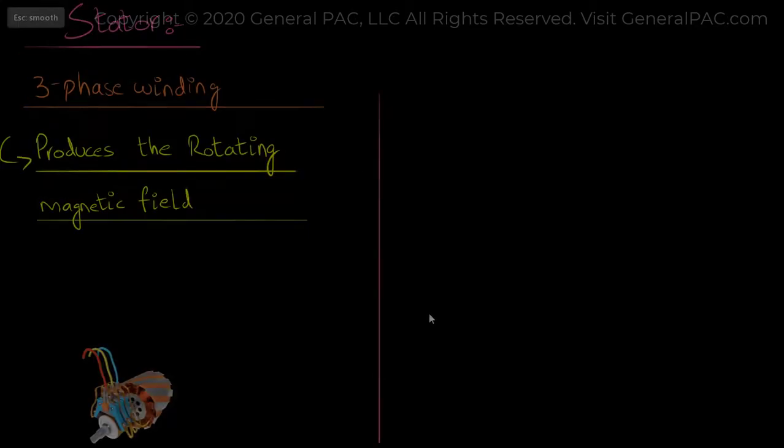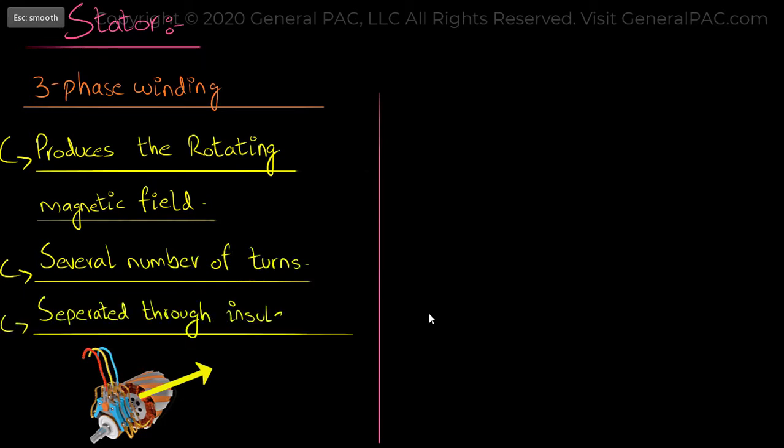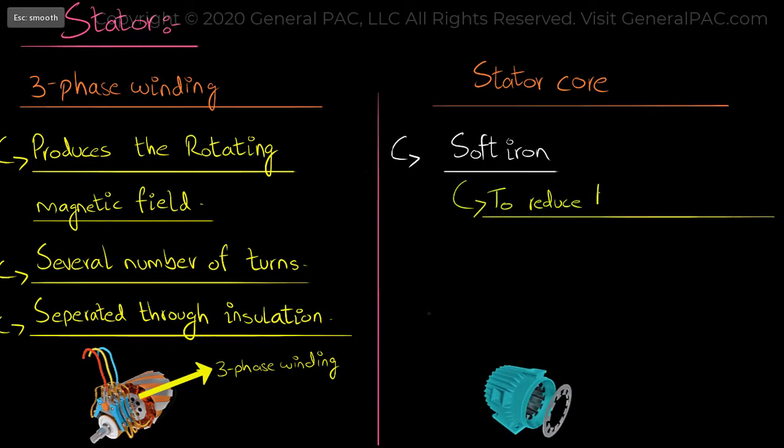Each of these phase windings have several number of turns and each turn is separated with the other through insulation. As we know that flux passes through a metal easily as compared to air, to complement the stator windings we have the stator core which consists of soft iron in order to reduce hysteresis losses and it is laminated so that eddy current effects can be reduced.